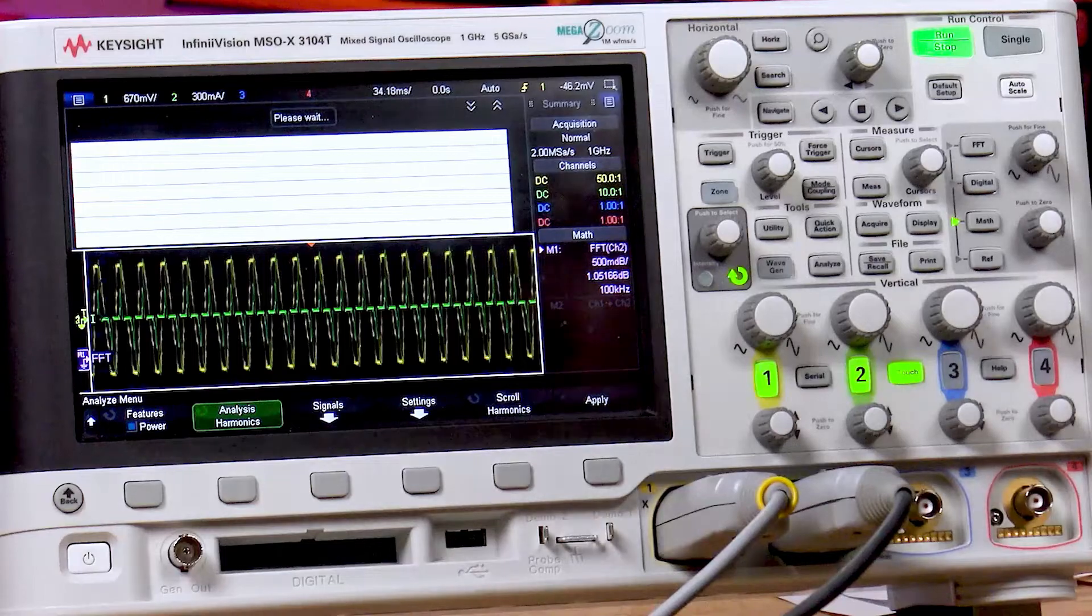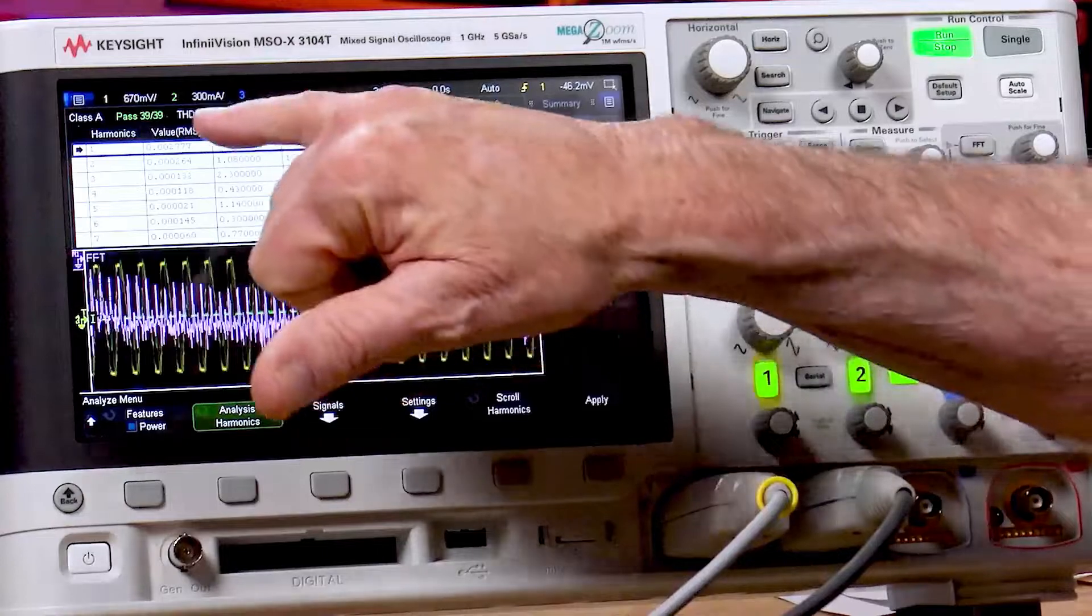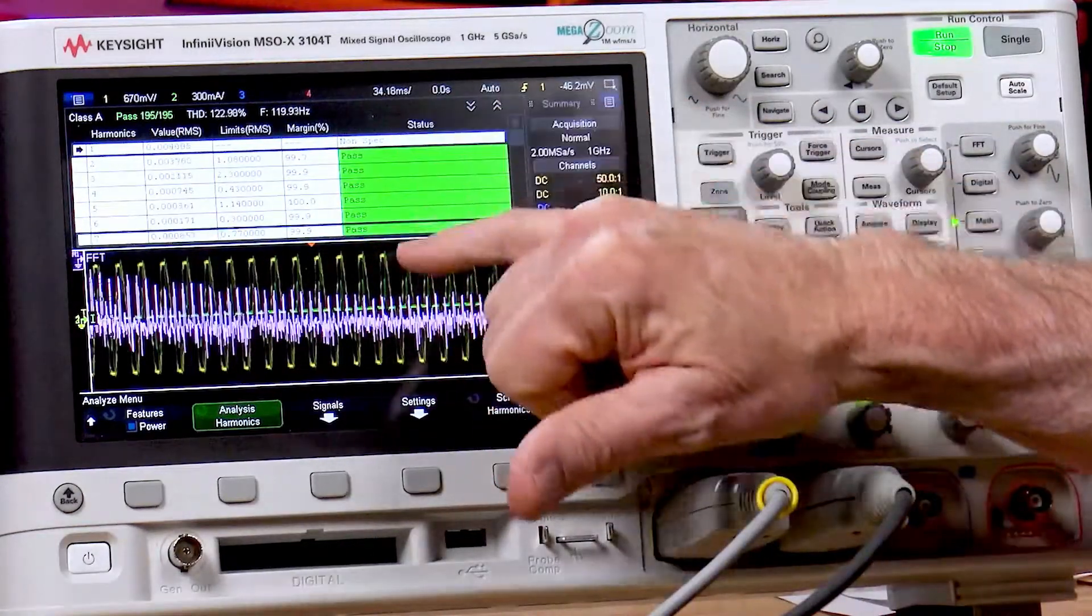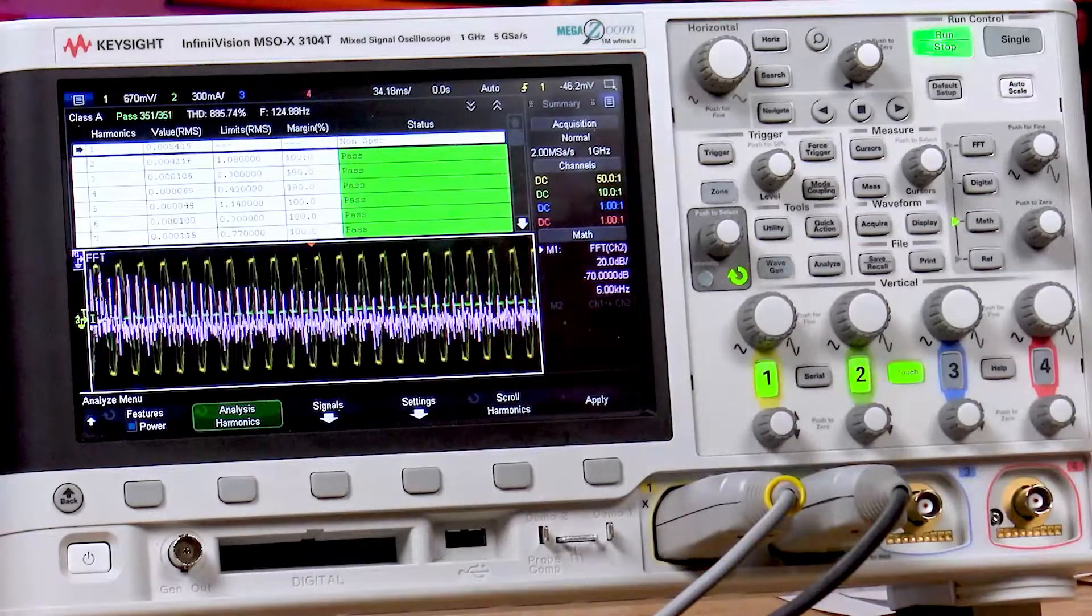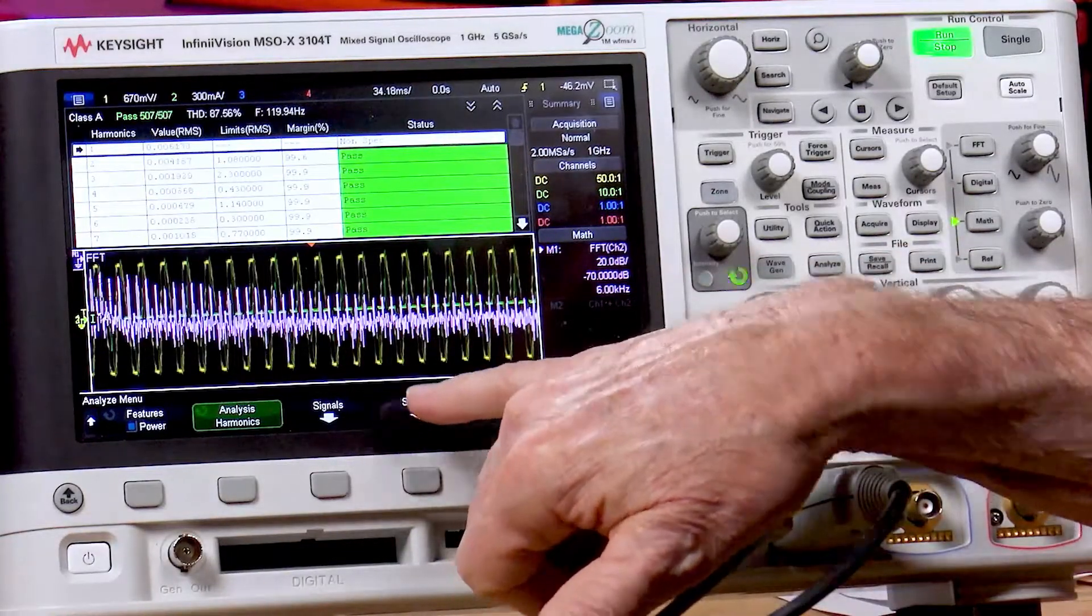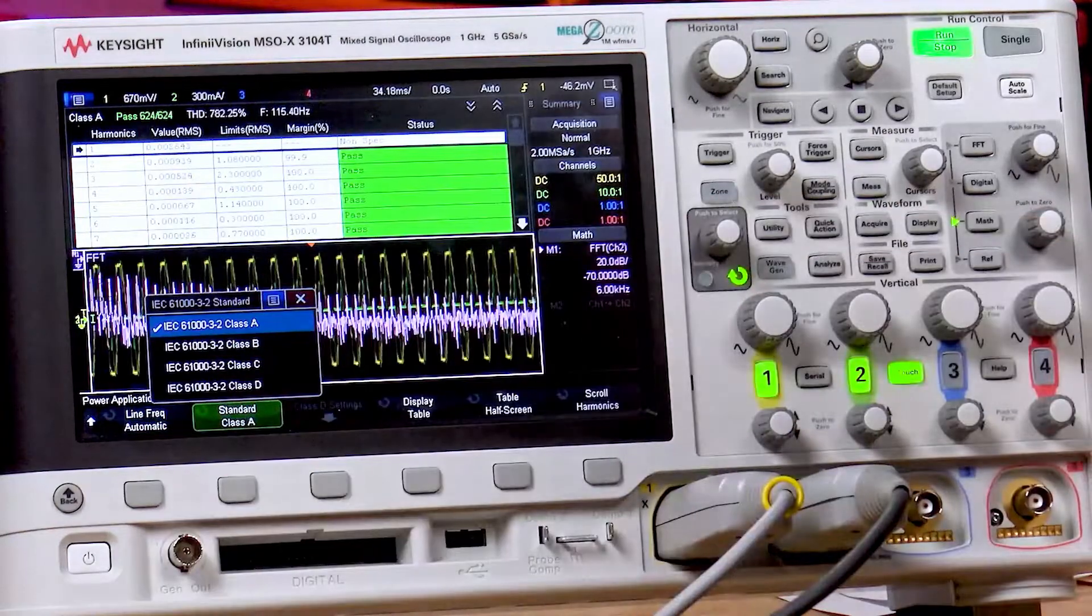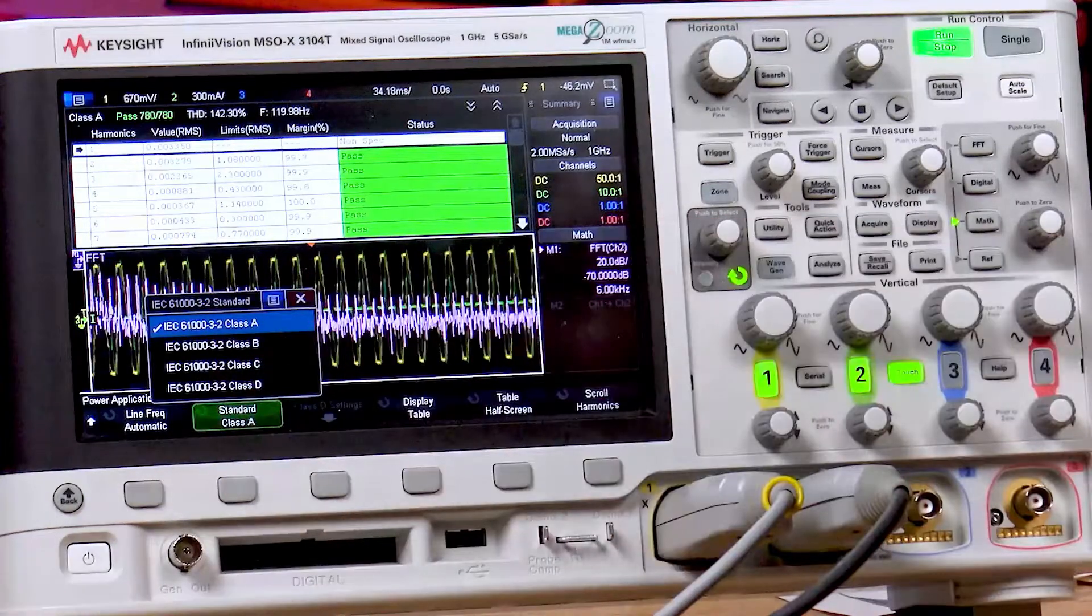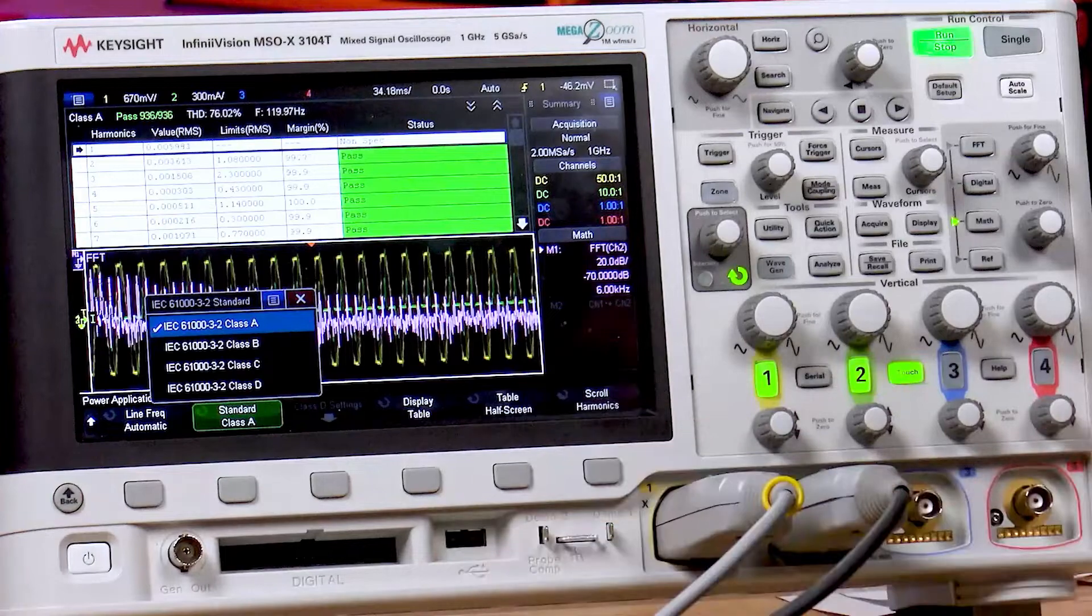It's going to run an FFT on the current waveform, and then bring up a table here that's Pass-Fail. Here you can see we're all passing. The purple waveform is the FFT on the current waveform. And you can select different types of compliance settings. It's based on the IEC 61000-3-2. Right now, we're doing a Class A compliance test up to the 40th harmonic.